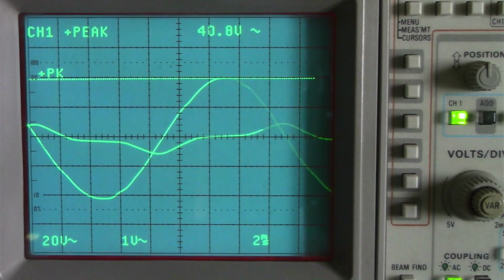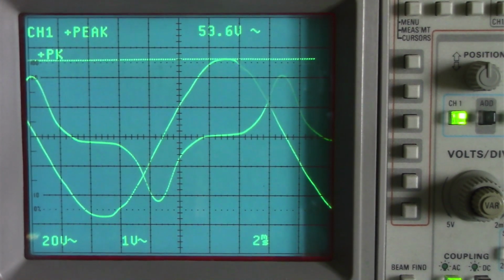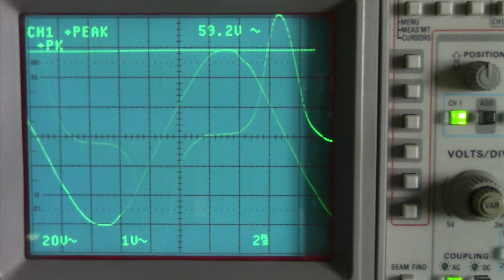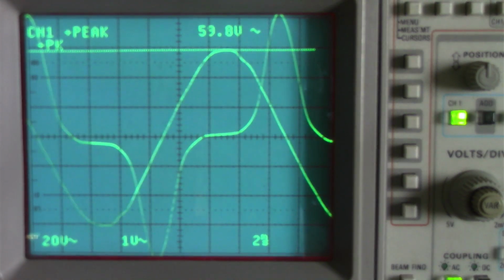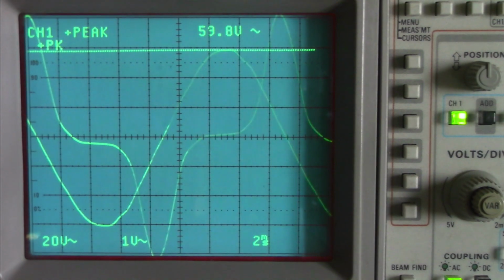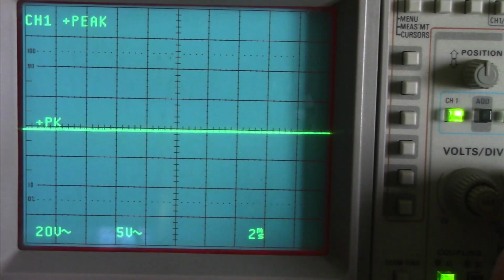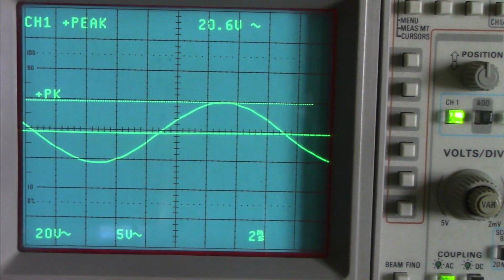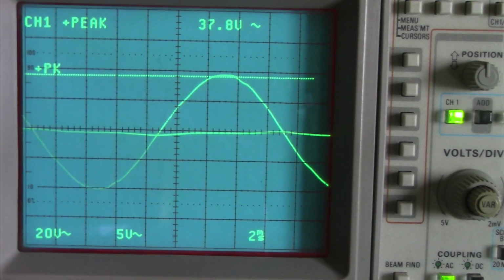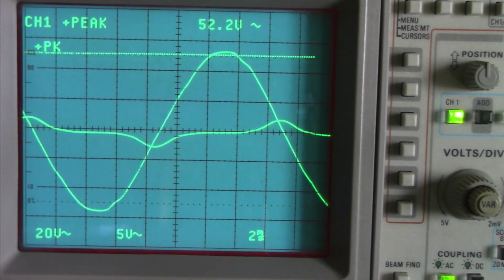Watch what happens when we go to 60. You can see that current just rockets up. We now have over 4 amps peak going into that transformer winding. Let's set channel 2 to 5 volts per division. Here we are with 20 volts into the transformer, 40 volts peak, 60 volts peak.